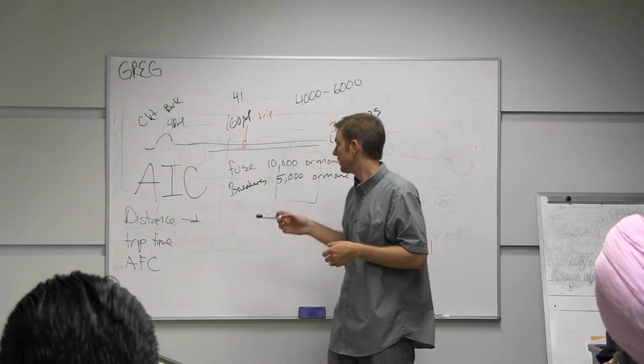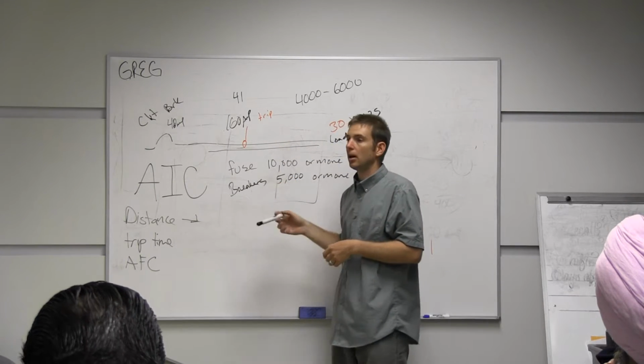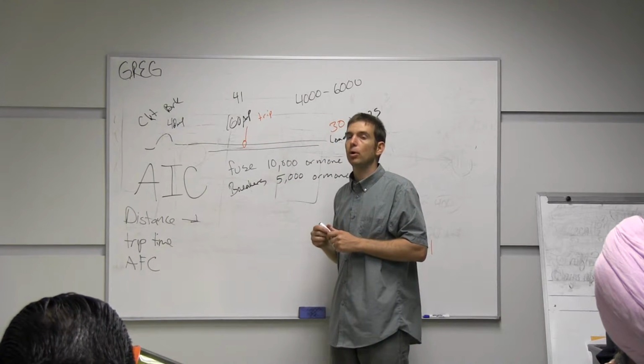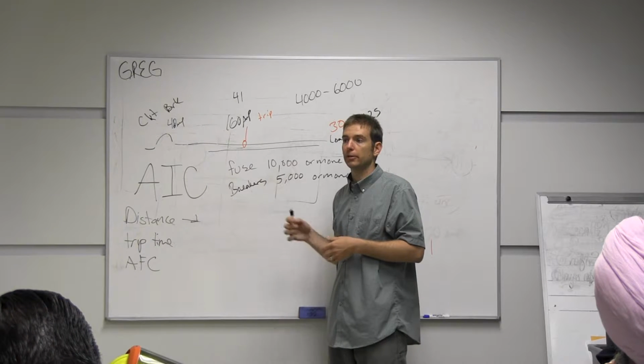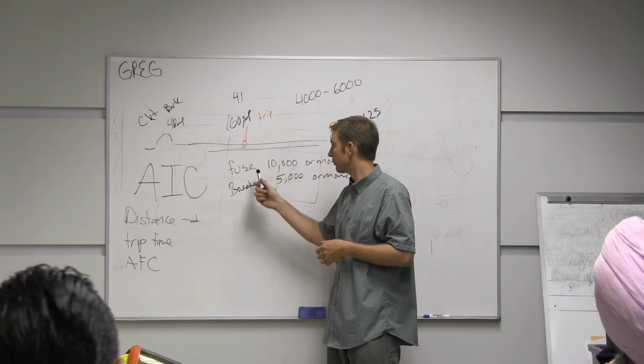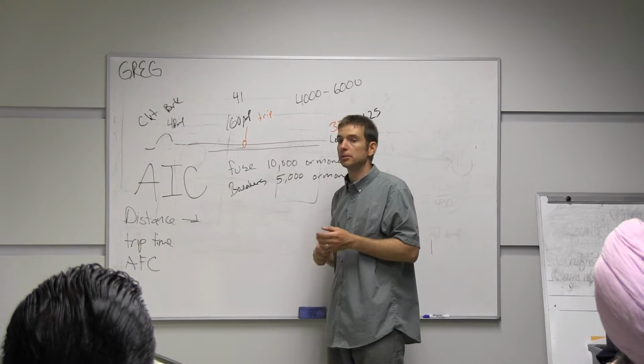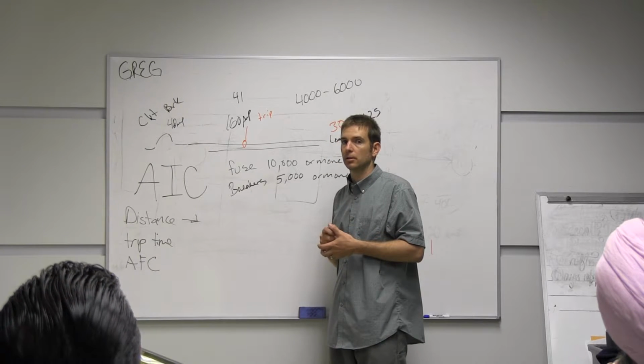You need to make sure that you put the right AIC back. You need to also make sure that the right voltage is being put back. If you have a 600 volt panel or a 600 volt fuse or circuit breaker, it needs to be replaced with a 600 volt.